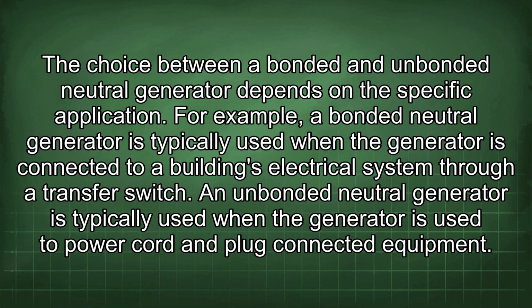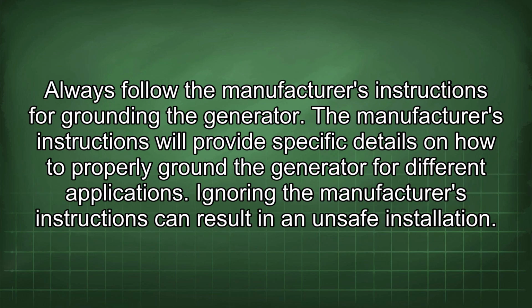For example, a bonded neutral generator is typically used when the generator is connected to a building's electrical system through a transfer switch. An unbonded neutral generator is typically used when the generator is used to power cord and plug connected equipment. Always follow the manufacturer's instructions for grounding the generator. The manufacturer's instructions will provide specific details on how to properly ground the generator for different applications. Ignoring the manufacturer's instructions can result in an unsafe installation.